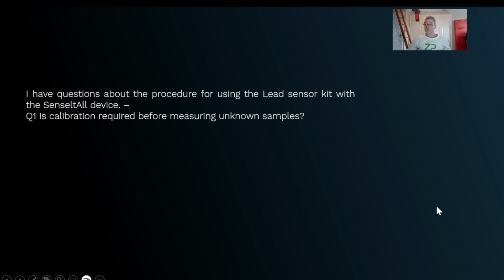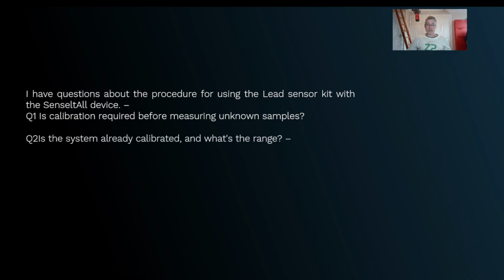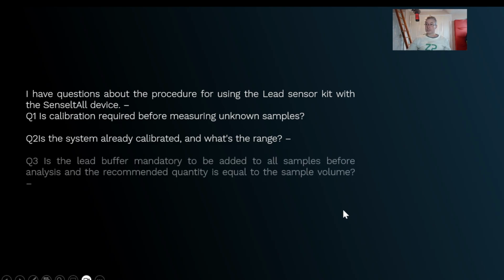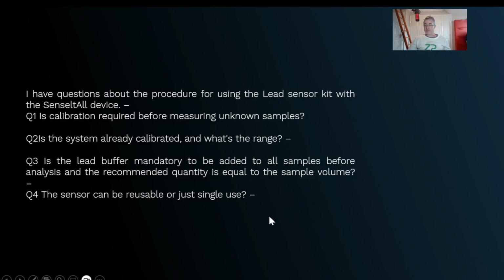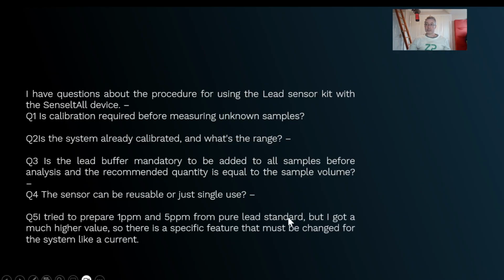So in summary, you don't need to calibrate unknown samples. The range is this: we can use dilution, and the higher the concentration, the more dilution we use. If you haven't used enough dilution, it will just say high for you, and then you can increase the dilution. Is the lead buffer mandatory? 99% of the time it is mandatory. Can the sensor be reused? It's single use.